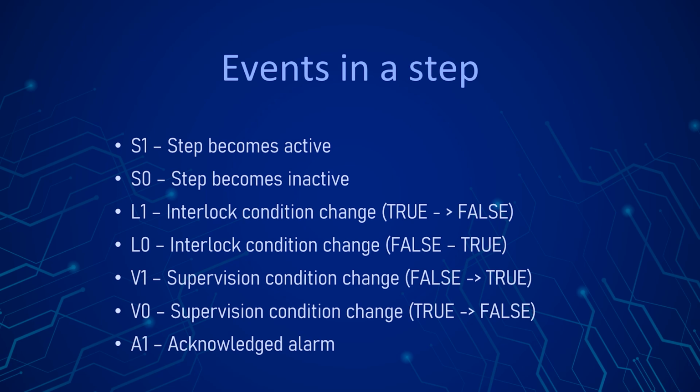Interlock and supervision have the acknowledgement requirement setting, which means that after they have the good state, the interlock condition is true, and the supervision condition is false. On the block interface you have to set the ACF input. This acknowledgement also has the event, A1.